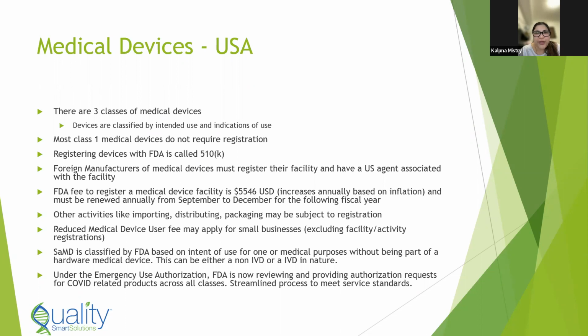Mostly similar to Canada, class one medical devices do not require registration. However, when you do want to register a device, you would have to go through the 510K process for registering devices. For foreign manufacturers, you must register your facility and have a US agent associated with that facility.